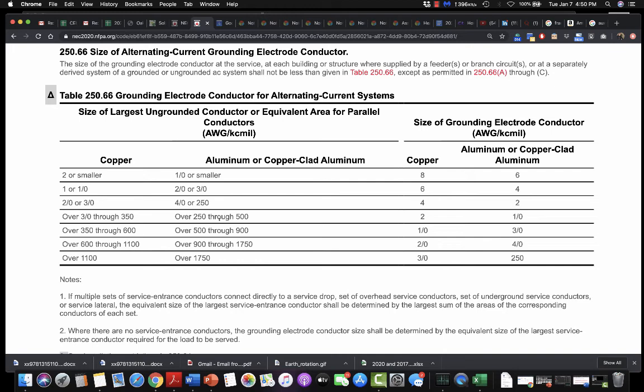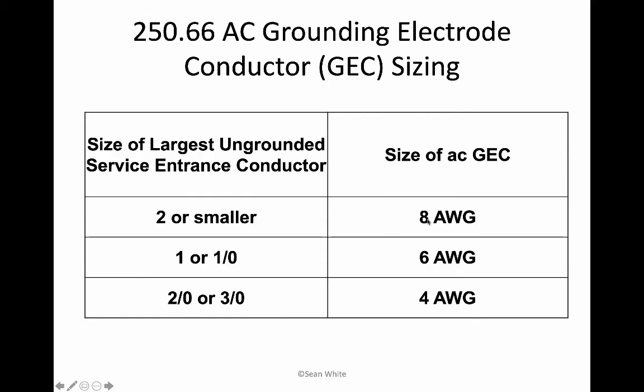How big does that thing have to be? And it's based on the largest ungrounded conductor. And then you will have to look at this table. And so if your wire is a 1 or a 1/0, then it needs to be at least a number 6 copper. It never can be smaller than a number 8. And that would be if your largest ungrounded service entrance conductor was a 2 or smaller. And then you can see that it gets bigger and bigger and bigger.